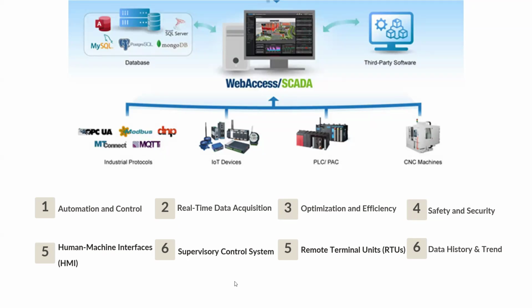SCADA uses the HMI for the operators to monitor and control. We call it HMI, as you all mentioned, the human-machine interface. So SCADA means supervisory control system. It will supervise the control area and take the right action. Usually for remote areas and long distances, RTUs, remote terminal units, will be used. These kinds of controllers will be set far away, in the oil field, for example. It will take a control action and send the signal to the HMI or to the operator console. And again, it will collect the data as a history, and you can have your own trends and history.